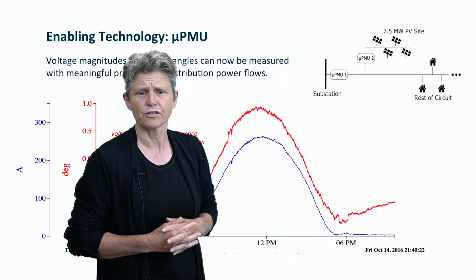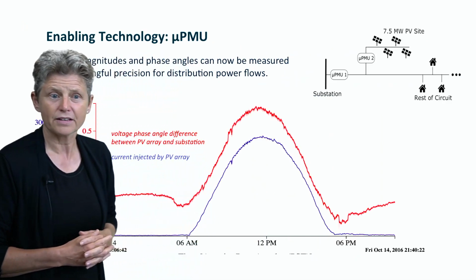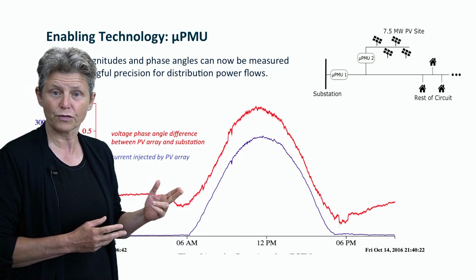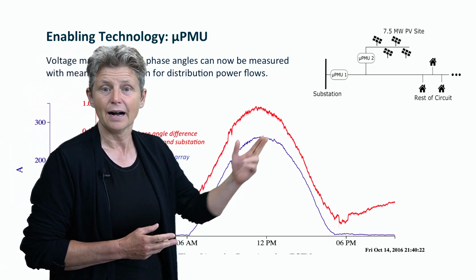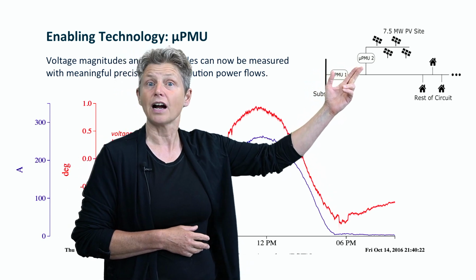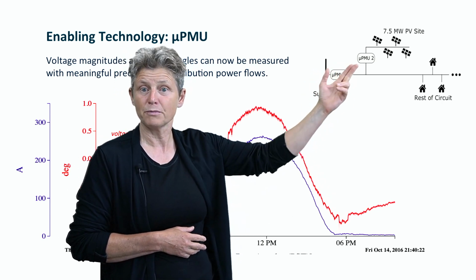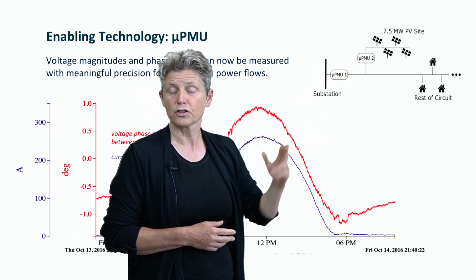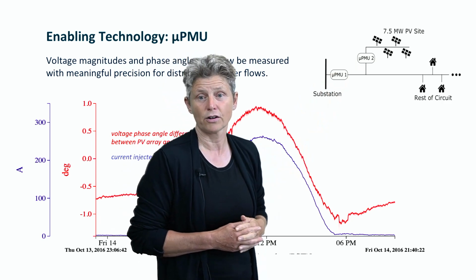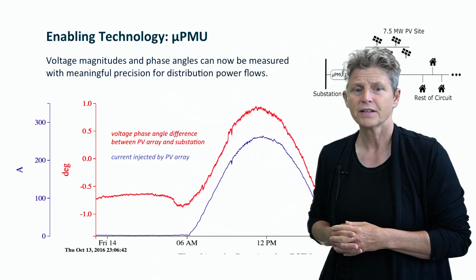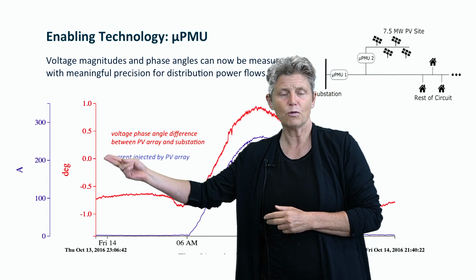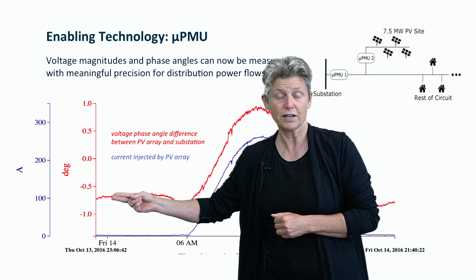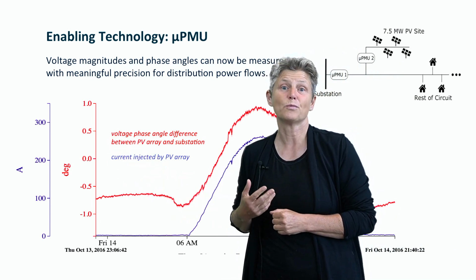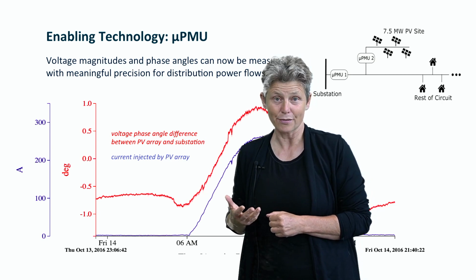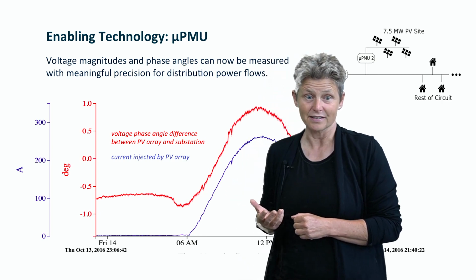Here's an illustration of some measured voltage phase angle differences. In this case, it's the difference in the timing between the voltage at micro-PMU 1 and 2 when there's power being generated by that large solar PV plant. And you can see that we're talking about less than 1 degree of angle. So that's less than 1/360th of a 60th of a second.